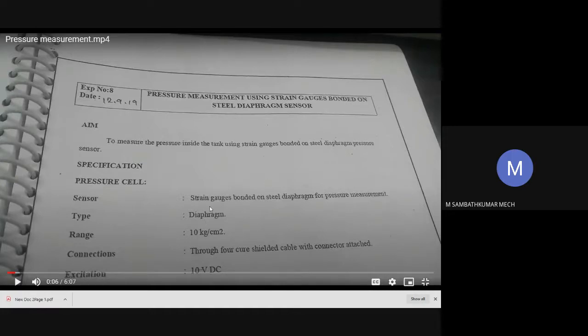The pressure cell specification: it is a strain gauge bonded type sensor. The type is diaphragm and the range is 10 kg per centimeter square. You can convert it into bar. The connection is through a 4-core shielded cable with a connector attached, and the supply is 10 volt DC, not an AC supply.